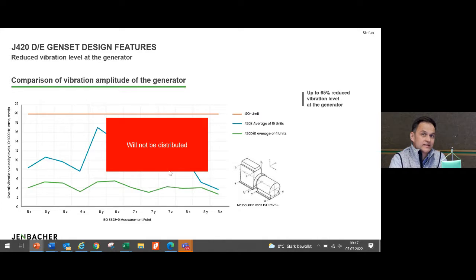On this slide, you can see that the generator vibrations are reduced by up to 65% with the new arrangement system, due to the fact that we have now implemented the high flex coupling, the engine on feet, and the generator rigidly connected to the generator frame. This really enabled a reduction of up to 65% in vibration levels on the generator.